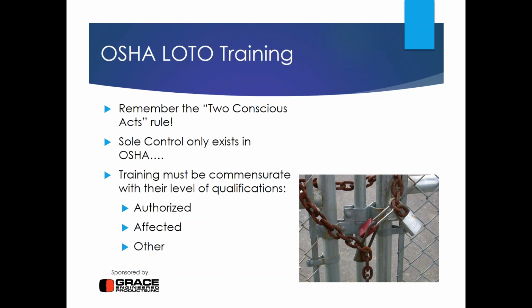So I'm going to mention this because whenever we encounter situations where you can't do lockout, the device will not accept the lock, or it would be unsafe to use that device for switching, I will just refer you to the Two Conscious Act rule. So kind of file that in your mind, and this is also relevant to tagout. If you look at the OSHA standards, when you are not able to lock out, you're going to do tagout, and then the code will say that you're going to do one additional measure equivalent to a lock, and that is really the idea of the Two Conscious Act rule.